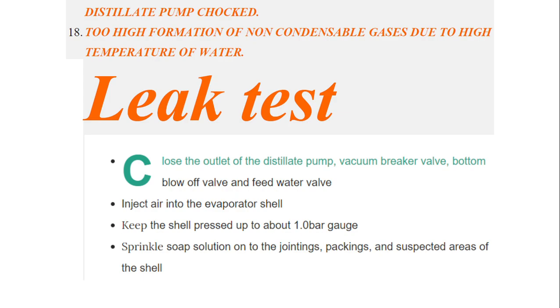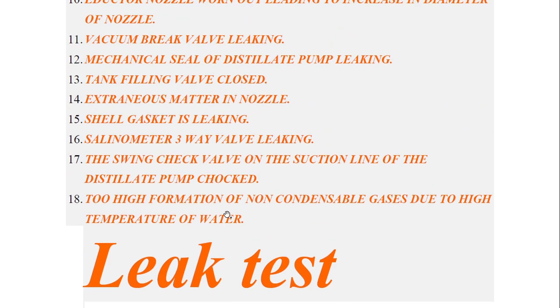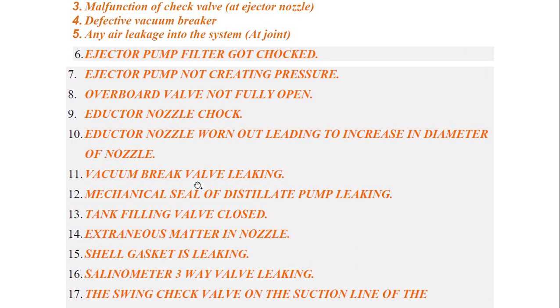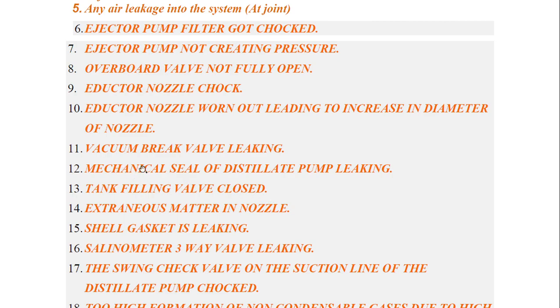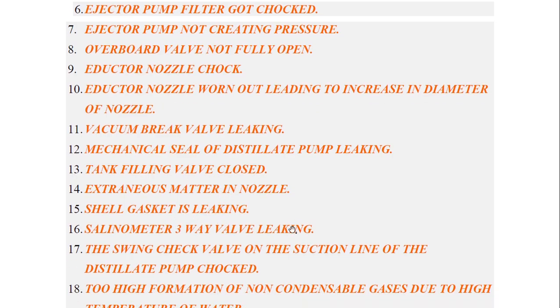Inject air into the evaporator shell — obviously we are carrying out the leak test through air, not water. We keep the shell pressurized up to about one bar gauge. We watch the reading and it should hold at one bar. Now, we sprinkle soap solution on all the jointing areas — wherever we have gaskets, joints, the vacuum break valve, filling valve — to check for leaks.